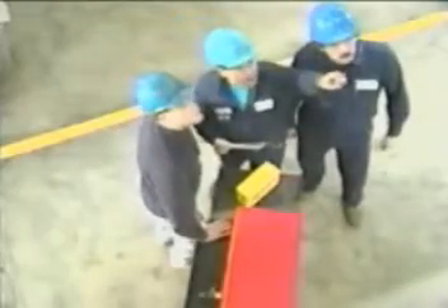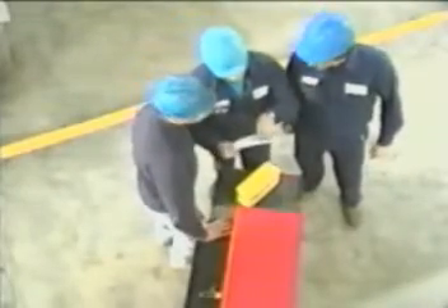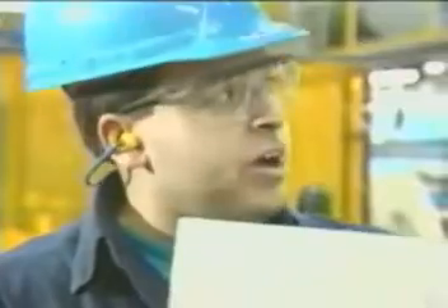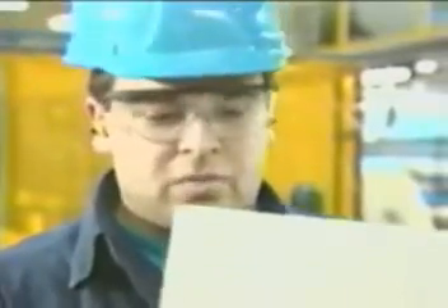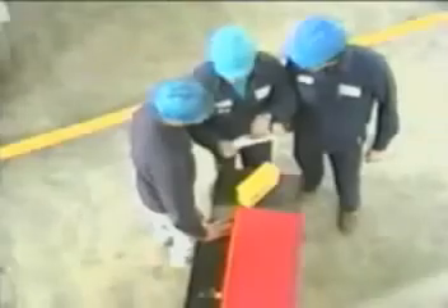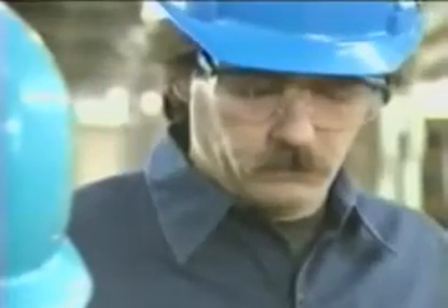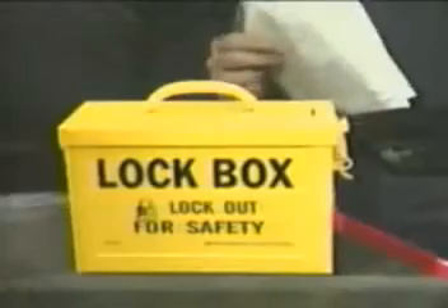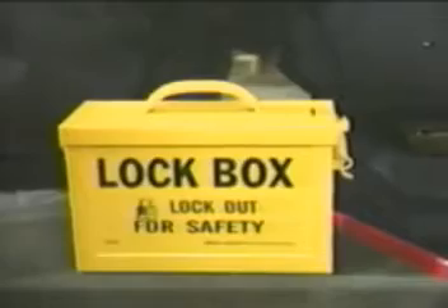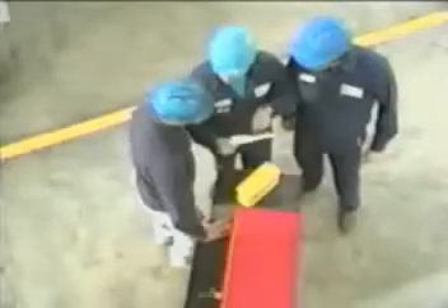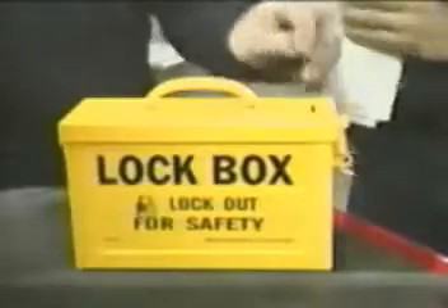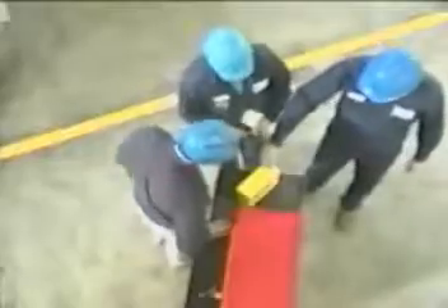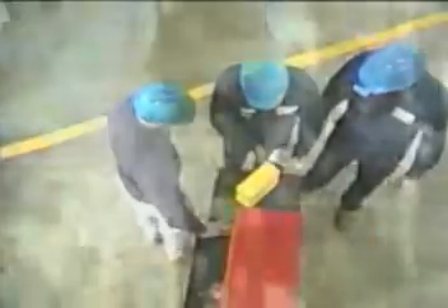are protected. Larger jobs involving a number of workers, for example a whole crew or department, will require special lockout procedures that are supervised by a single authorized employee. At any point in time, the entire procedure must remain under their authority and control. In such instances, a special lockbox may be used to keep all keys. Be sure to follow your employer's established procedures concerning group lockout.